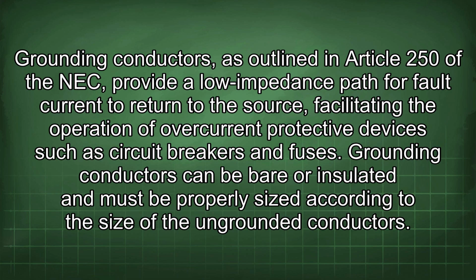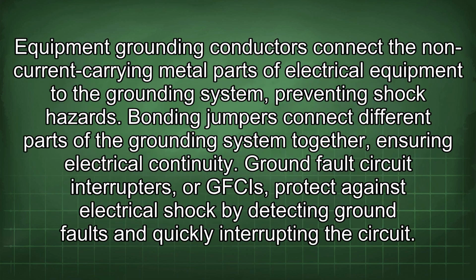Grounding conductors can be bare or insulated and must be properly sized according to the size of the ungrounded conductors. Equipment grounding conductors connect the non-current carrying metal parts of electrical equipment to the grounding system, preventing shock hazards. Bonding jumpers connect different parts of the grounding system together, ensuring electrical continuity. Ground fault circuit interrupters, or GFCIs, protect against electrical shock by detecting ground faults and quickly interrupting the circuit.